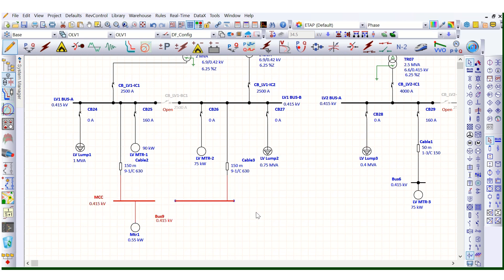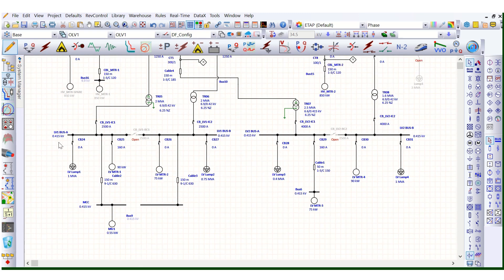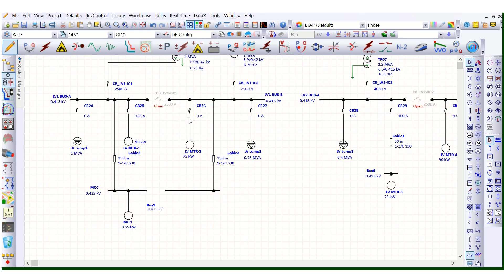To summarize: if the power requirement at the remote MCC area is much higher than or equal to the PMCC area, then that area should be considered the load center, and the distribution transformers should be installed near that switchboard. I hope this video has added some value. If you have any suggestions or doubts, please put them in the comment box and I'll get back to you. Thanks for watching.